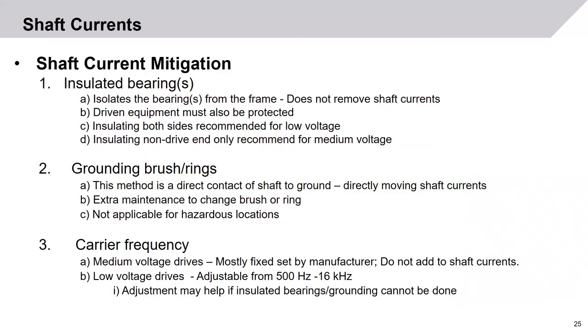To mitigate shaft currents, the first step is insulated bearings. Insulated bearings isolate the bearing from the frame; however, they do not actually remove the shaft current — it will still be there, so the driven equipment must also be protected. In low voltage motors, insulating both sides of the bearings is recommended. However, in the medium voltage world, only insulating the non-drive end is recommended.